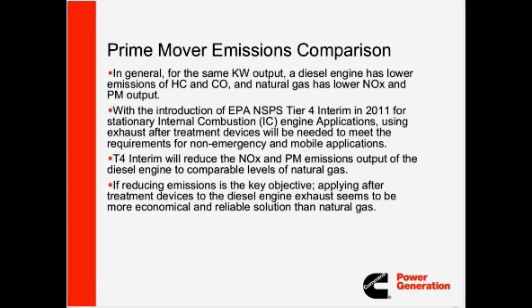So what you end up with is the high torque capability of diesel and all the advantages of diesel generator sets, lower hydrocarbon and carbon monoxide, and acceptable NOx and PM emissions comparable to those of natural gas. Therefore, I would say if reducing emissions is the key objective, applying after-treatment devices to the diesel engine exhaust seems to be a more economical and reliable solution than natural gas, especially for standby applications.